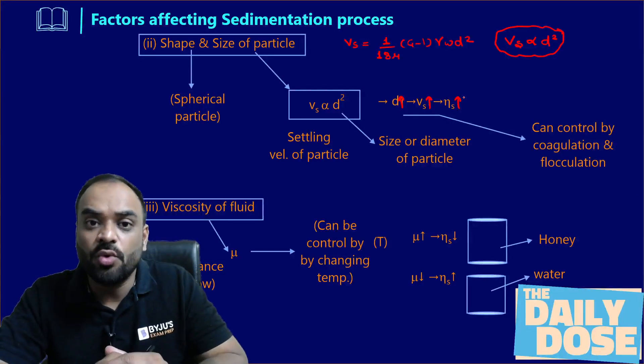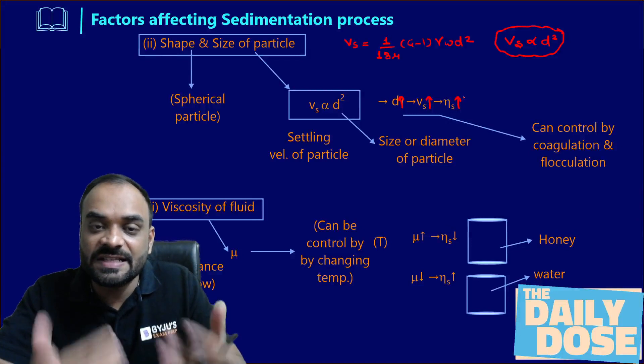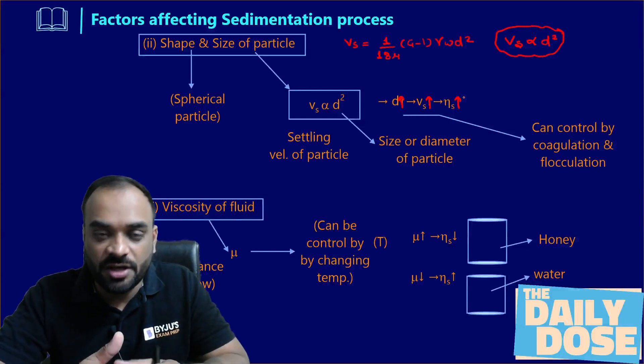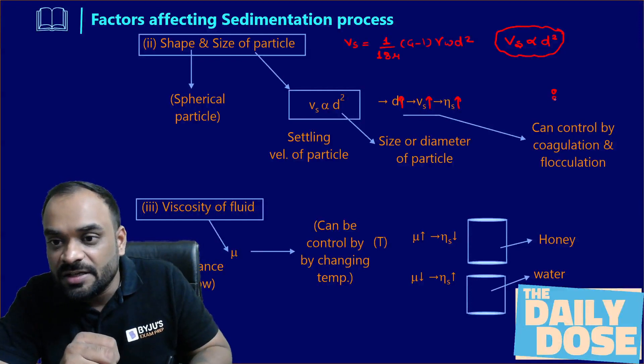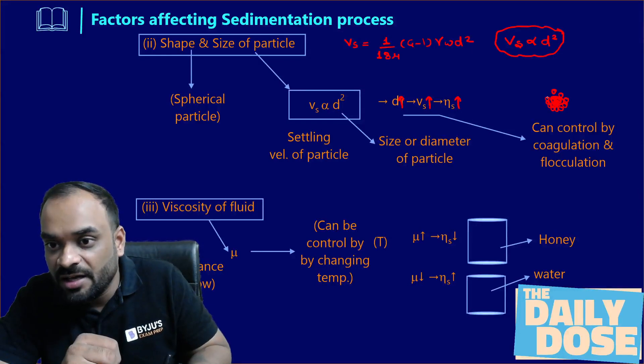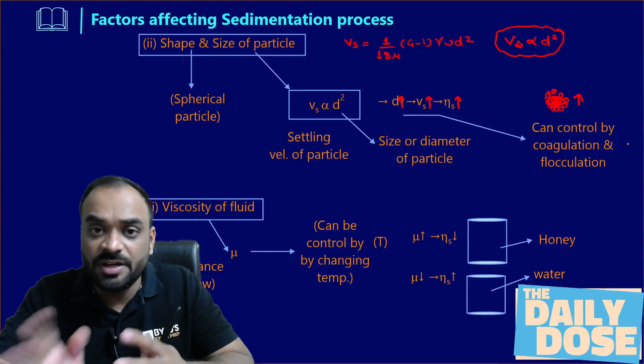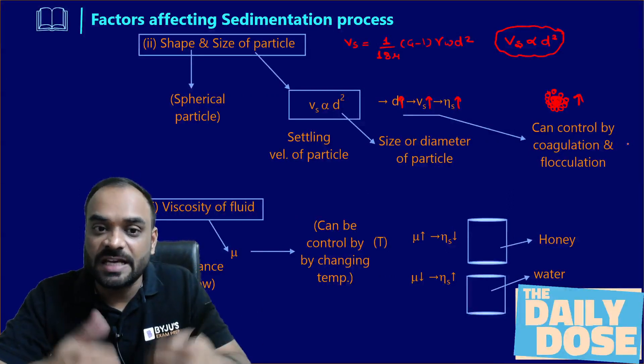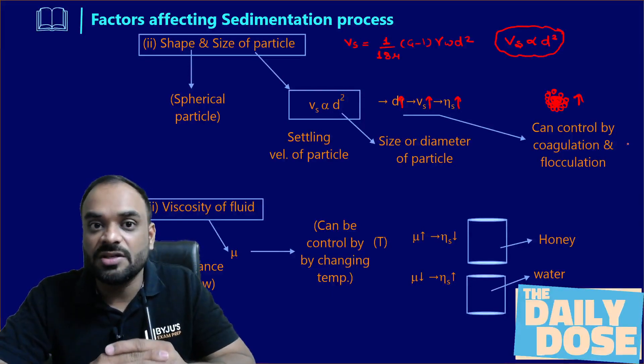The question is: how can we increase particle size in our treatment plant? The process we use is coagulation and flocculation. We add a coagulant into the water so that it generates some sticky material, and over that sticky material, smaller particles attach. The smaller particles attract onto it and ultimately the size of the particle gets increased. This process — coagulation and flocculation — allows us to control the size of particle in our water treatment plant.